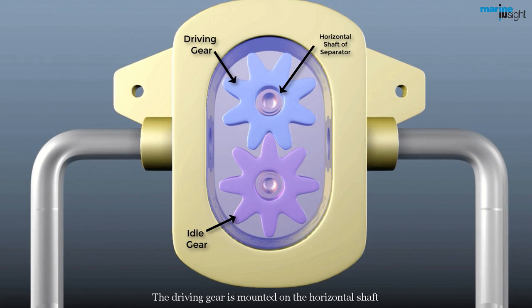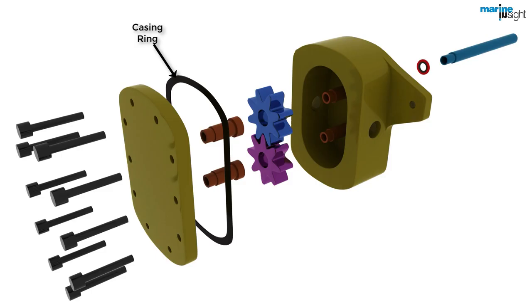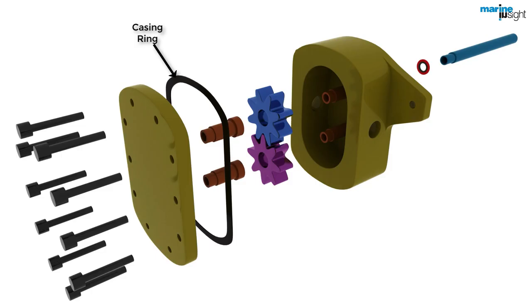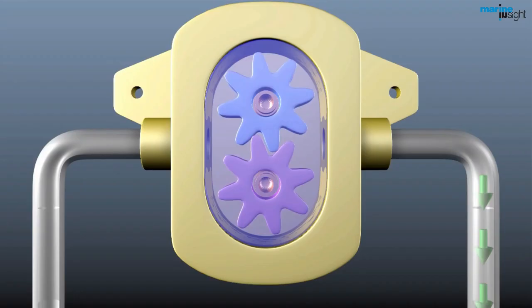It comprises of idle gear and a driving gear. The driving gear is mounted on the horizontal shaft. The body of the gear is provided with a casing ring and the horizontal shaft end is provided with a sealing ring. These rings will not allow the fuel oil to leak outside the gear case or towards the purifier lube oil sump. Each gear sits on a bush for proper fitting and rotation.